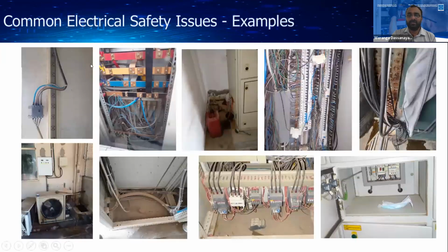Here are photographs. This is my experience during some site visits. You can see the first image. The breaker is directly mounted on a wall without any enclosure. So if someone goes and touches this breaker, definitely he will die, because there is no barrier or obstacle at this termination point. There is no cover. The circuit breaker is just directly mounted on a wall, and the terminations are open to touch. The second picture.